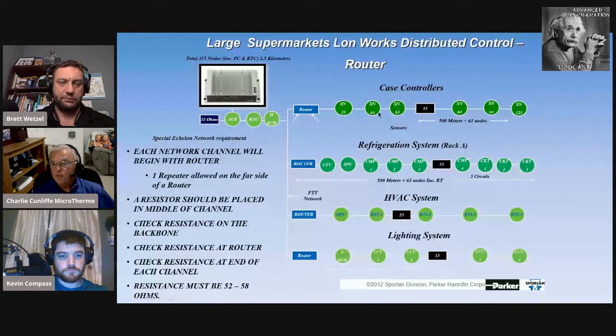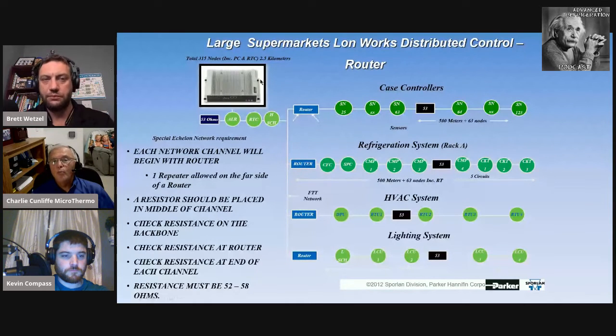All we do is service pin it when we get it there. That associates back to the HMI, and all of the parameters - whether it's superheat, whether it's back pressure, whether it's controlling the gas cooler - all of those control parameters are flashed to that smart node, or microcomputer.